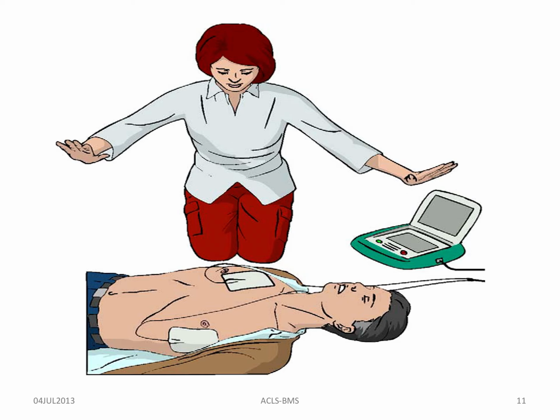Once you do the shocking, please remember that when you are doing the shocking, you should keep your arms and your body away from the patient, otherwise you also will get a shock.